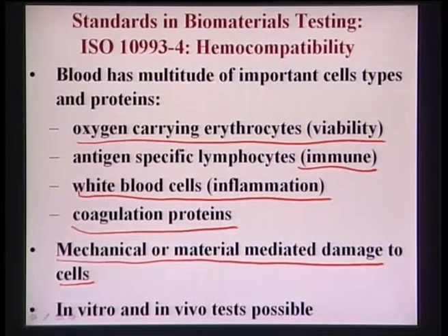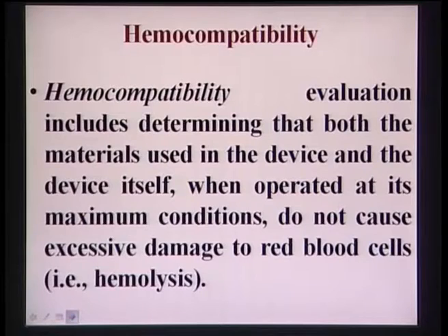Now, one can do this blood compatibility test both in vitro as well as in vivo. Again, in vitro means the laboratory simulated test, and in vivo means the experiments which are conducted inside the animal. This is more specific information on hemocompatibility, and this particular biocompatibility test includes determining that both the materials used in the device as well as the device itself, when operated at its maximum conditions, should not cause any excessive damage to RBCs or hemolysis. Again, you have to underline this excessive damage.